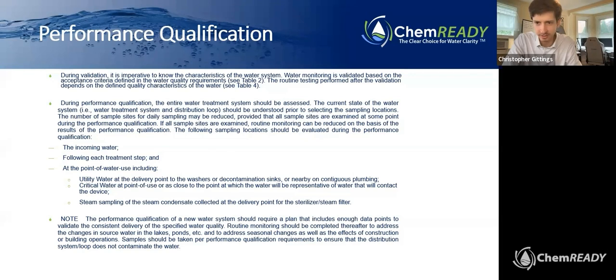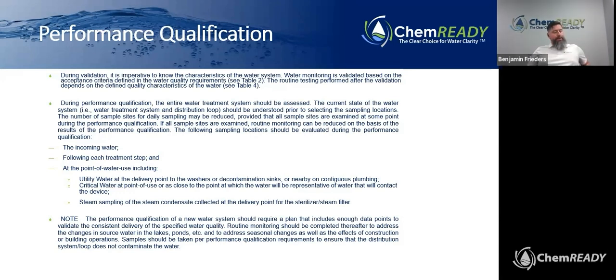Great. R. Chavez asks, what is the testing cadence? Just colony and endotoxins? Daily sampling can be done by staff? Water strips? Sure. One section we did not talk about is the continuous ongoing water quality monitoring. Performance qualification is the first 12 months after the installation of your water treatment equipment. After that, there are sections, and there's table 4, table 5, and table 6 in the standard. The frequency and the parameters that are tested are, I believe, pH, alkalinity, hardness, chlorine and turbidity, TOC, bacteria and endotoxin for critical water.